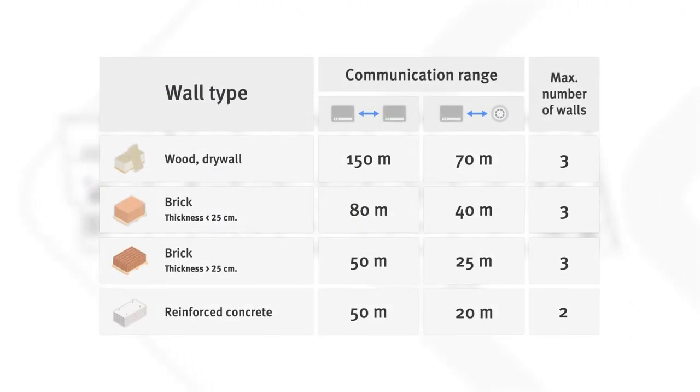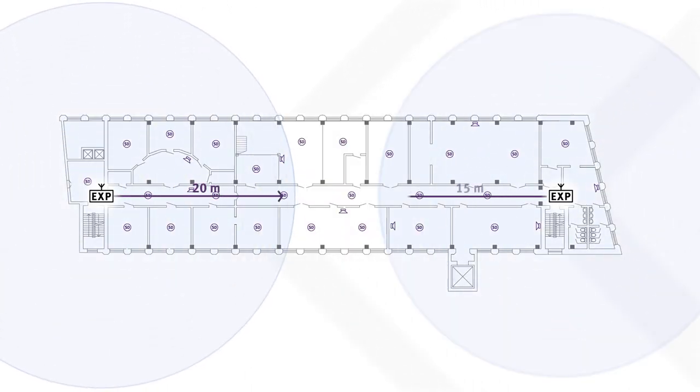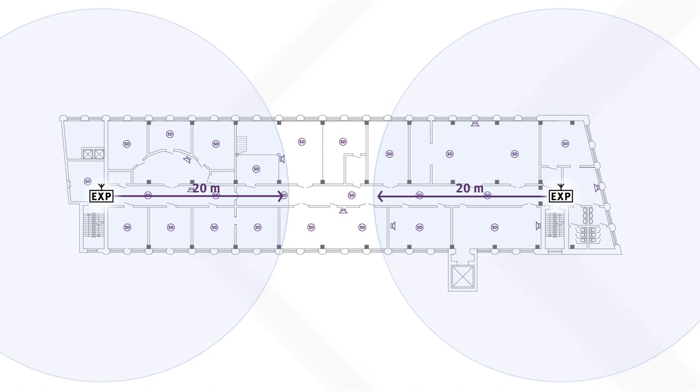Next, check the expected communication range using the table from the manual. In our case, the range is limited to 20 metres and two walls. Create two circles around the expanders with a radius that corresponds to the communication distance. In the centre of the floor, there's a small area left without network coverage. Put another expander there and create a circle to indicate its range.